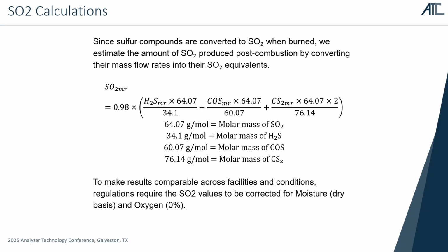And then, of course, with multiple flares, multiple fuel gases, CO boilers and SRU incinerators, each of them will have an SO2 value, which are then totaled for the facility total SO2 emissions that can be reported annually as well. When we're talking about regulations, keep in mind that for the Reg 88 example, we require the SO2 to be corrected for moisture, so dry basis, to standardize across facilities, and to 0% oxygen. Typically we've seen anywhere from 10 to 15, but in this case 0% oxygen was required.